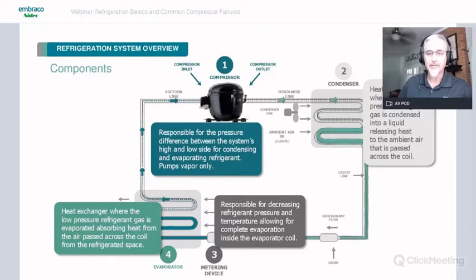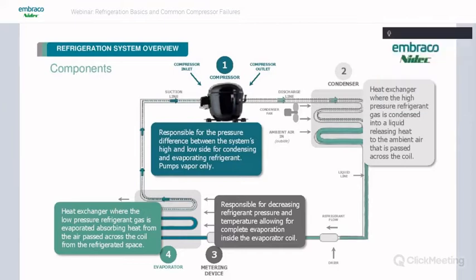So once it comes out of the condenser, we should have all liquid that's going to go down the liquid line to what could probably be called the fifth component that should be in every system, which is the filter dryer. We always want to see a filter dryer in the system. We'll talk a little bit about that later. But once we go through that, this liquid will come to the metering device. And the job of the metering device is to decrease the refrigerant pressure and temperature, which is going to allow for complete evaporation inside the evaporator coil. So when it hits the evaporator coil, we should have it ready to evaporate completely. And the evaporator is the heat exchanger where the refrigerant gas is evaporated. And as it does this, it's going to absorb the heat from the air passed across the coil from the refrigerated space.